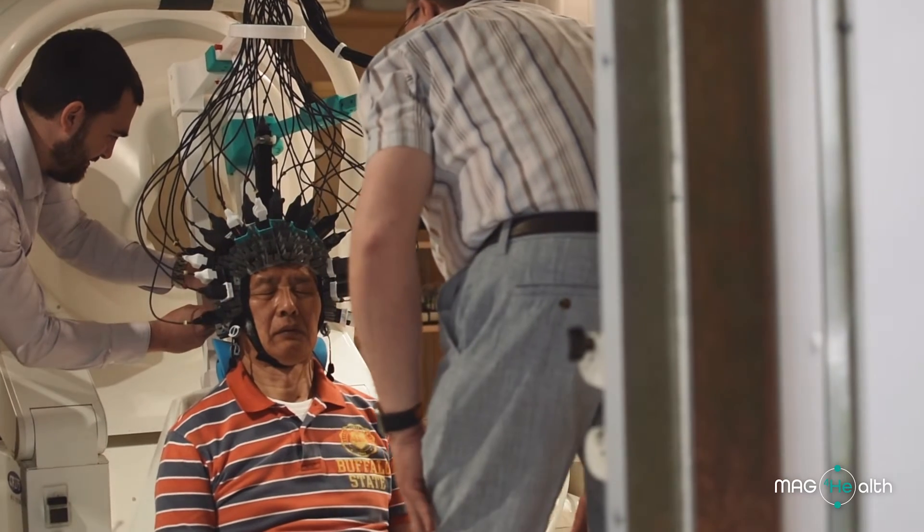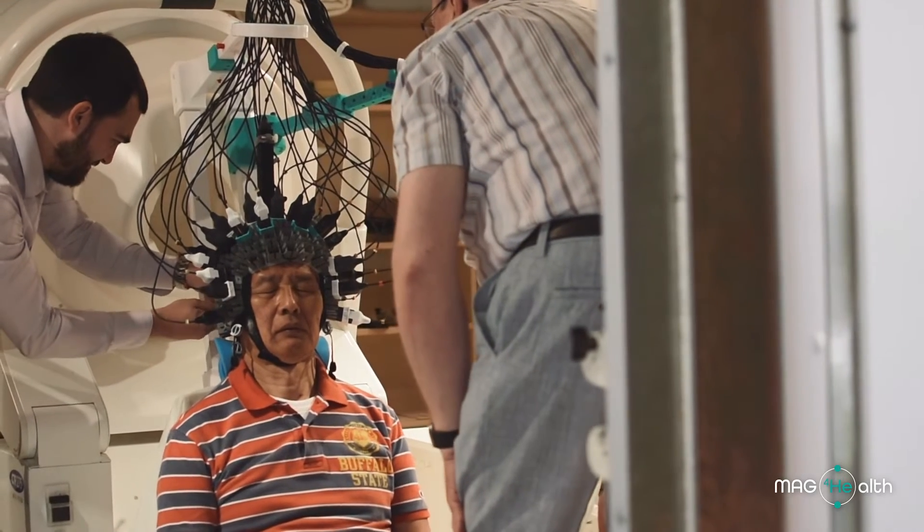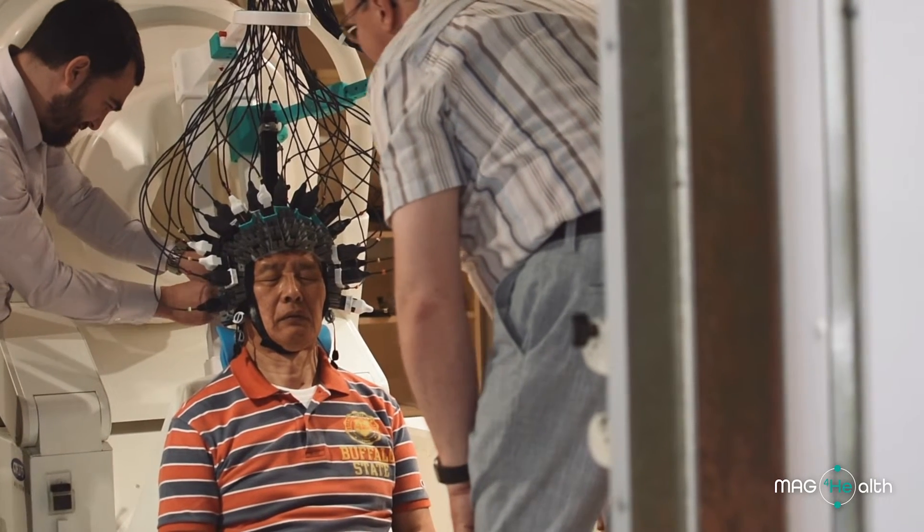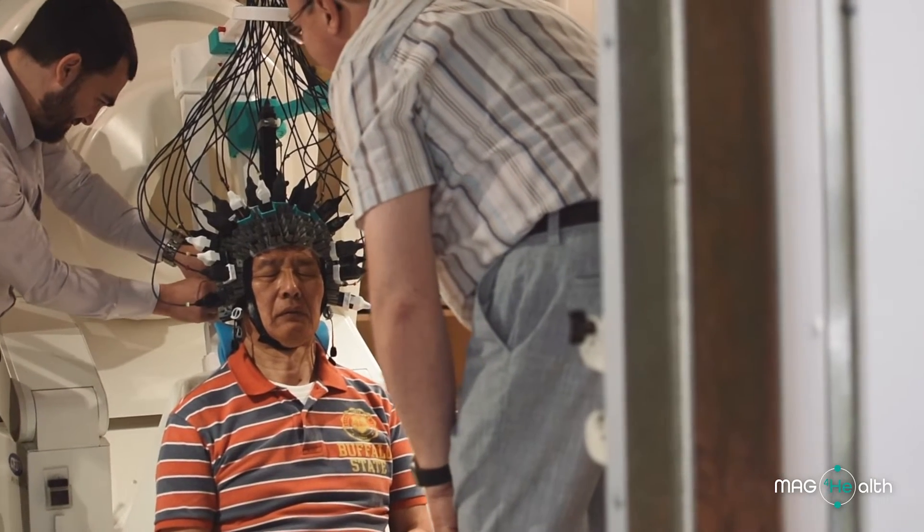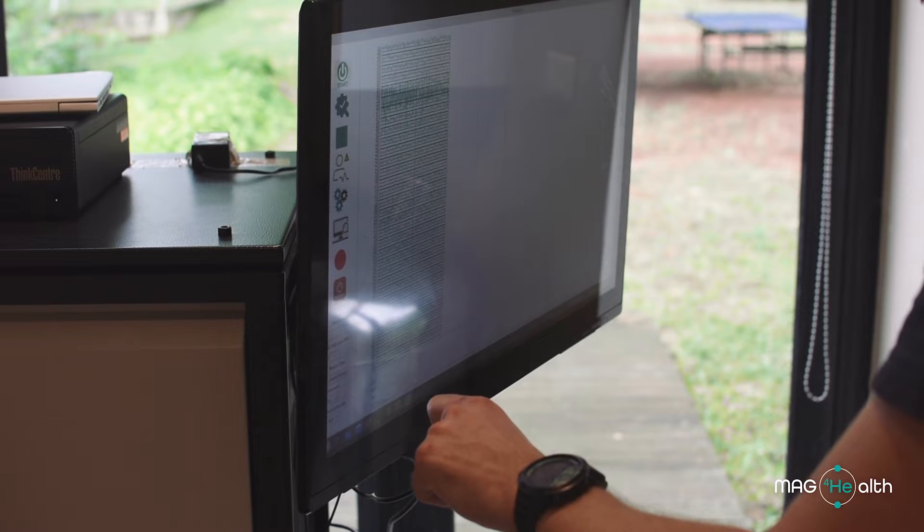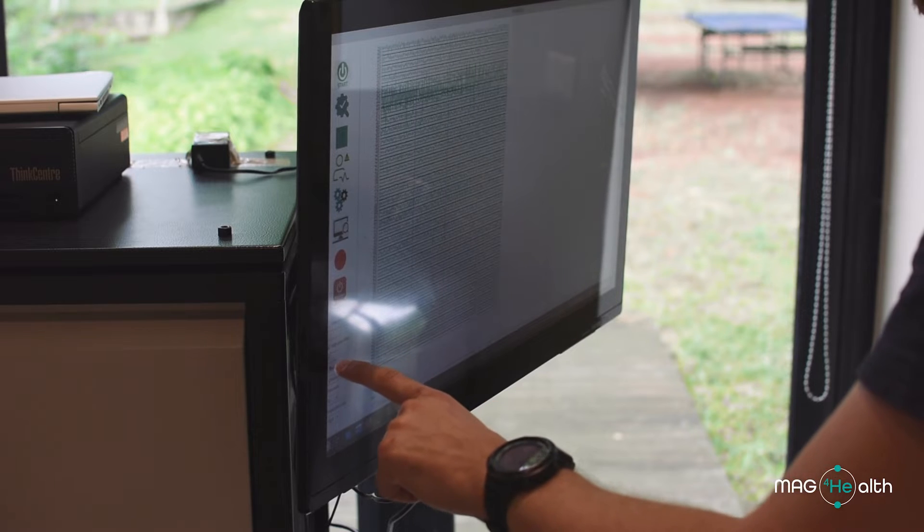This OPM system is very flexible to attach to the head. In the case of SQUID MEG, they cannot get the magnetic field directly. On the other hand, this OPM system is able to attach to the head directly.